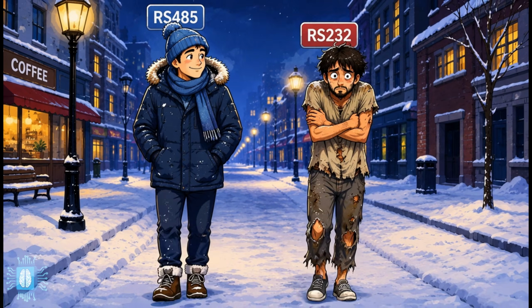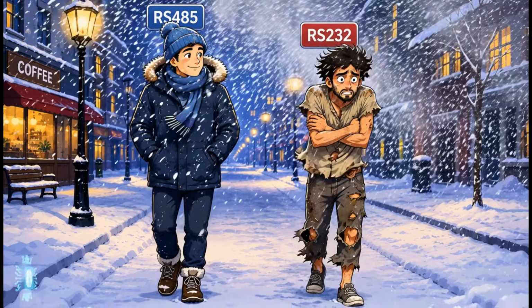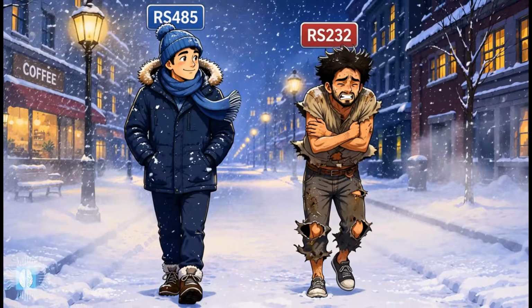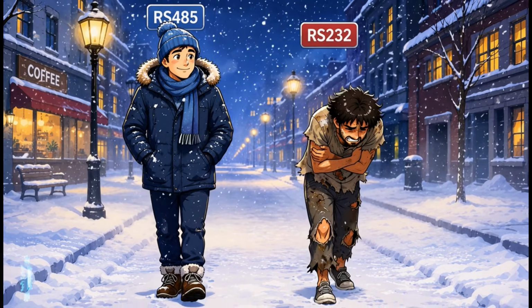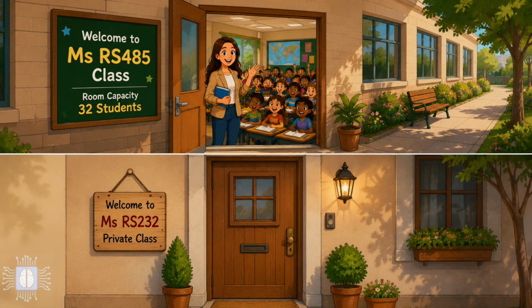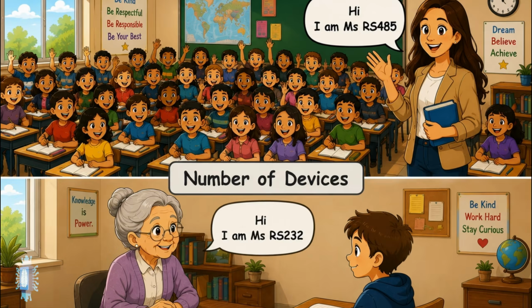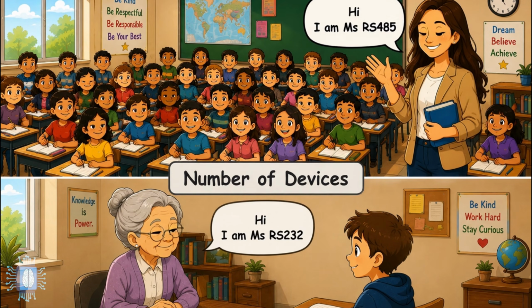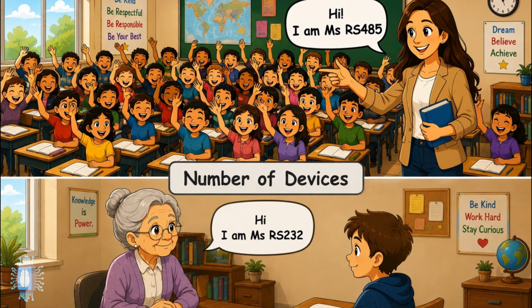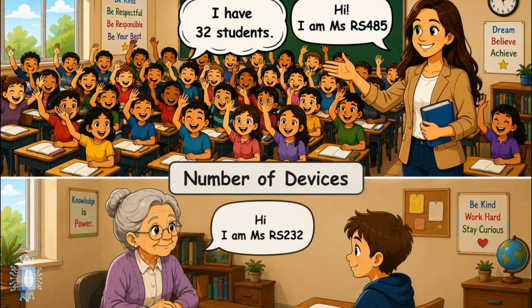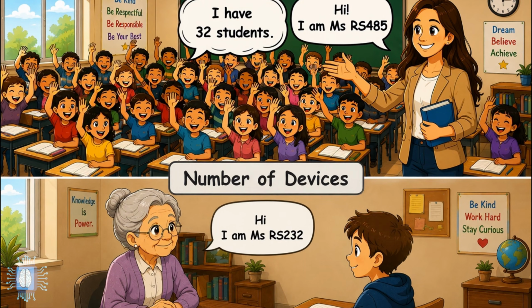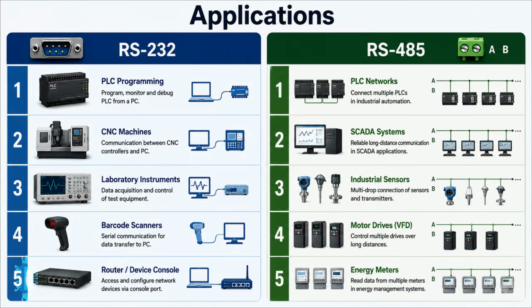When it comes to noise immunity, thanks to its differential signaling mechanism, RS485 is highly robust against electrical noise. If you need to communicate with a large number of devices, RS485 can support up to 32 devices on the same bus, whereas RS232 is a point-to-point communication standard that supports only 2 devices.